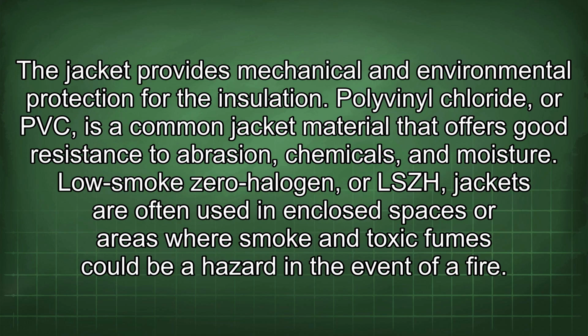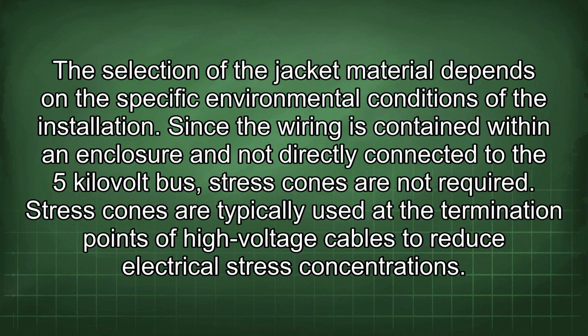The jacket provides mechanical and environmental protection for the insulation. Polyvinyl chloride, or PVC, is a common jacket material that offers good resistance to abrasion, chemicals, and moisture. Low smoke zero halogen, or LSZH, jackets are often used in enclosed spaces or areas where smoke and toxic fumes could be a hazard in the event of a fire. The selection of the jacket material depends on the specific environmental conditions of the installation.